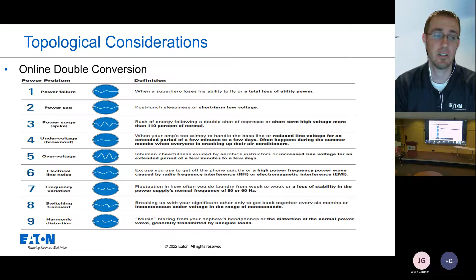Moving on to double conversion—you get all 5 things we talked about, plus protection for line noise, frequency variations, switching, transient, and harmonic distortion. That means pure clean power to your equipment with zero transfer time to battery. You might have sensitive equipment in some MDF locations where milliseconds matter, and with more expensive equipment you'll want that more robust protection.